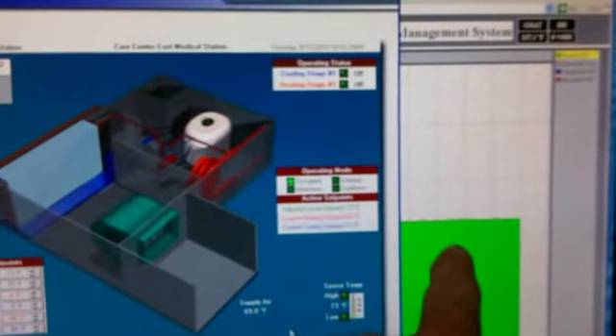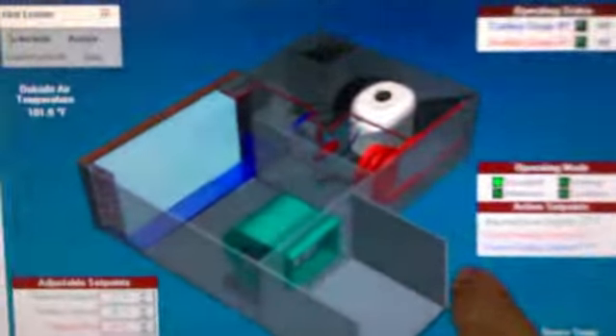Oh yeah. Before I reprogrammed these, this thing used to go up and down, up and down, up and down, about a 4-degree swing. They were pretty whacked out for a while. We needed some valve seals and valve actuators worked on, and then some reprogramming. The loops are doing good now. Of course, that's for the one building with the chillers. In our other building, we have just water source heat pumps.